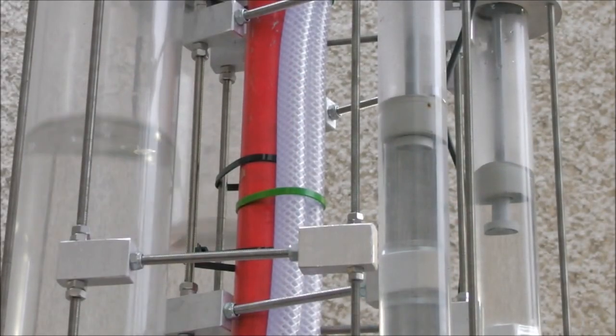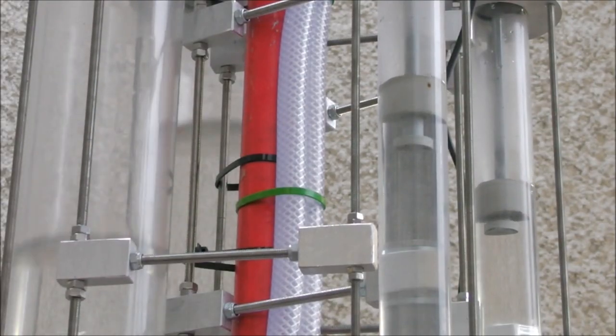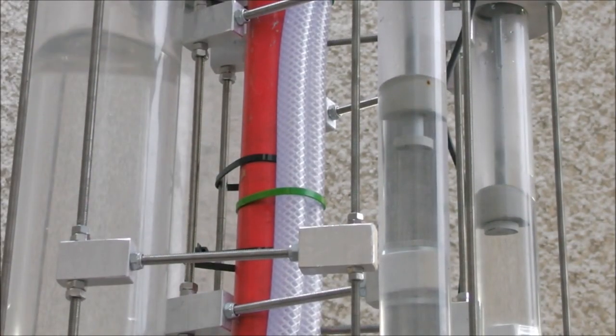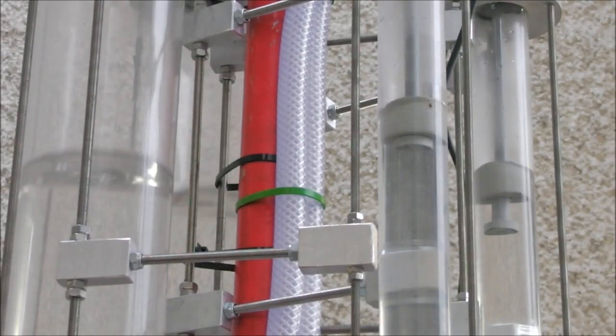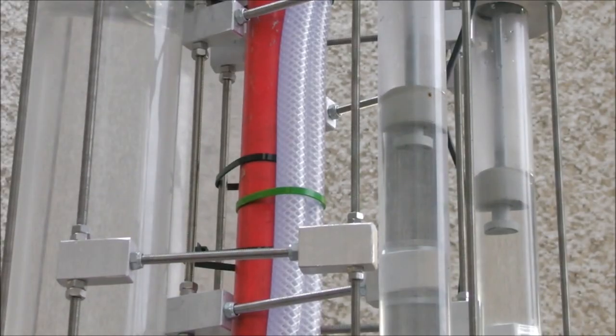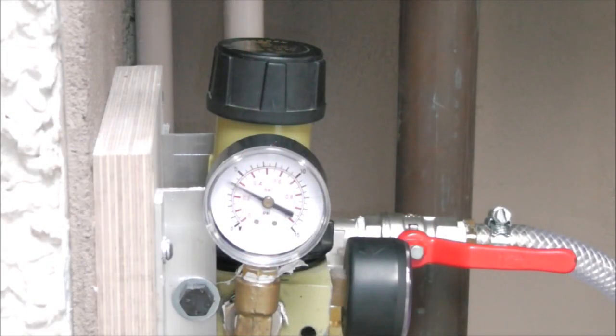There are two of these pneumatic motors mounted on either of the U-tube risers operating in antiphase. Each motor is alternately pressurized and vented to the atmosphere to create the oscillating motion that you see here. Pressurization and depressurization is controlled with two float switches and a couple of solenoid valves.